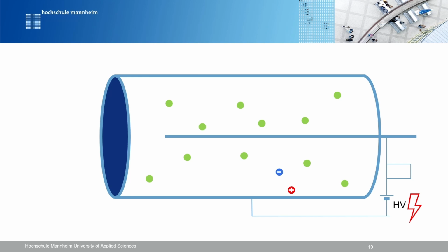The resulting positively charged fragments are subsequently accelerated towards the tube body. Negatively charged fragments, mainly electrons, are accelerated towards the anode wire. The closer the electron approaches the wire, the stronger it is accelerated. These fast electrons have enough energy to produce further ionization in the gas, resulting in an electron cascade propagating through the entire tube. These avalanches need to be controlled by a quench gas.